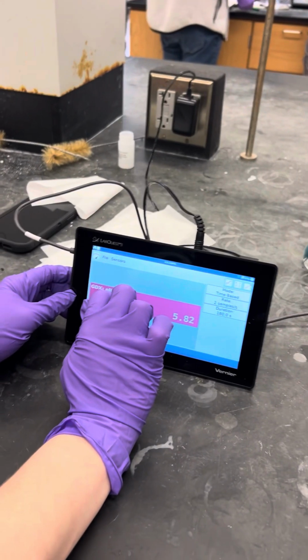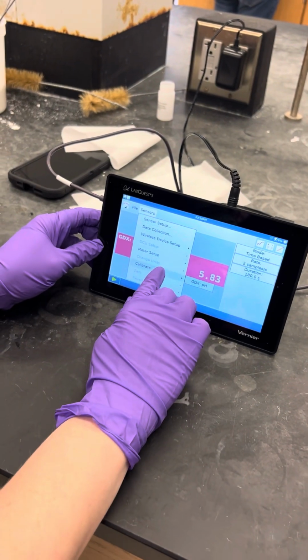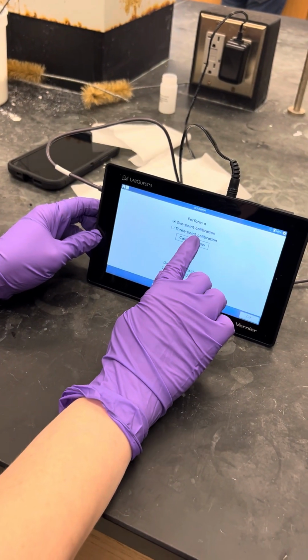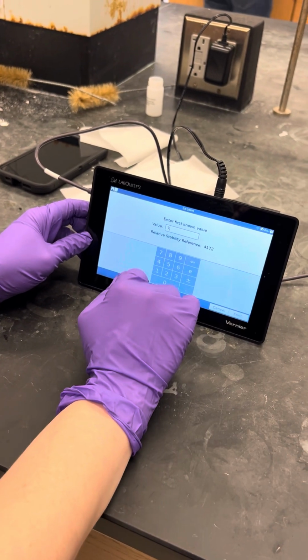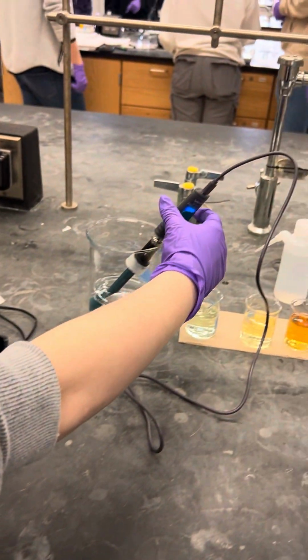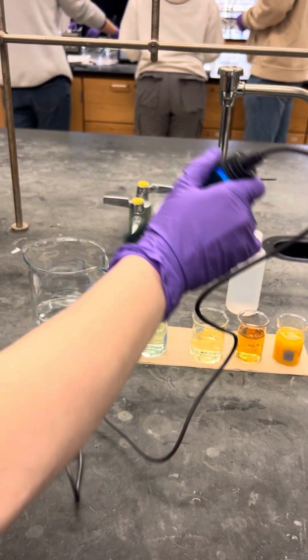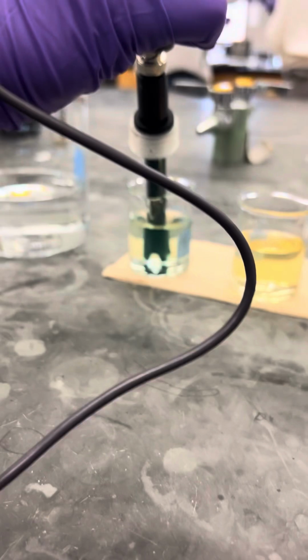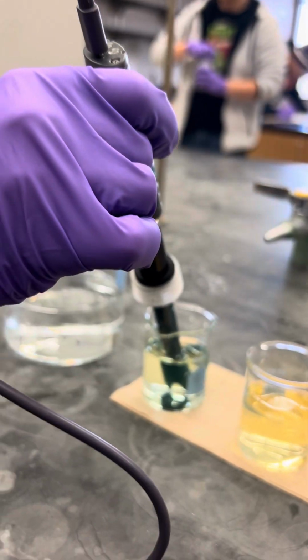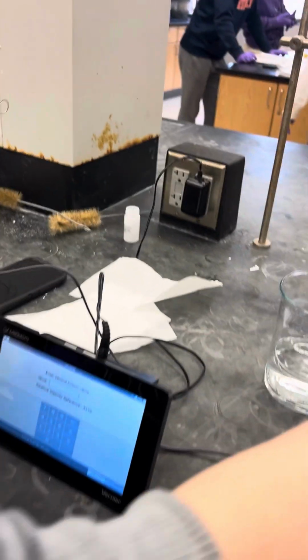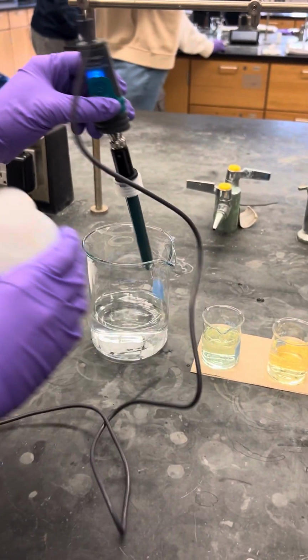Charles is going to be calibrating our pH meter. So first you hit sensors, calibrate, then pH. And we want to do a 2-point calibration. So first you input the value of the buffer that you will be putting it in first. And for us that was number 7. So she puts it in the buffer and then hits apply so the pH meter can calibrate.